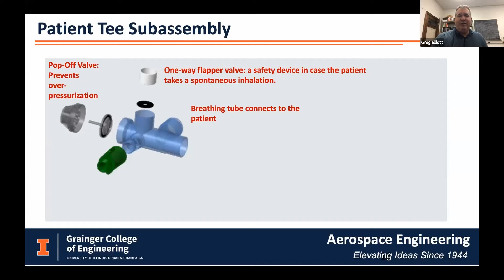And then finally, there was an adapter that was designed so that we could change the percentage of oxygen. Generally, this would be driven by pure oxygen, but a patient can only be on pure oxygen for so long before it starts to actually harm their lungs. And so by designing an ejector system, which uses principles in supersonic flow, we can draw in room air, so that we can decrease the percentage of O2 going to the patient. That was a device that would allow doctors to set that.